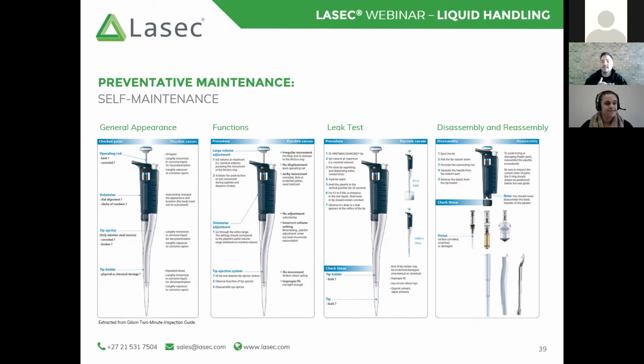The next function test that you're going to do is by depressing that push button to feel the movement of that piston, to feel if there's any sort of resistance, make sure that it's a smooth motion, okay? With pipetting and decreasing those sorts of human errors or performance errors, it is important that each pipetting step is as smooth and controlled as possible, okay?